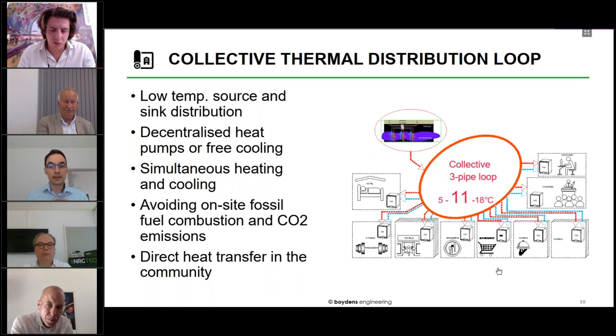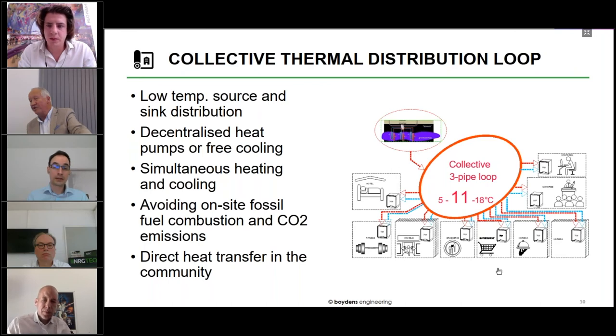The advantage of such a distribution loop is that it is at low temperature, so there are almost no line heat losses. It allows also for simultaneous heating and cooling in the system, which is compensated internally in the loop. It is also avoiding on-site fossil fuel combustion and CO2 emissions, and there is a direct heat transfer in the community, as already mentioned, between the heating and cooling part.